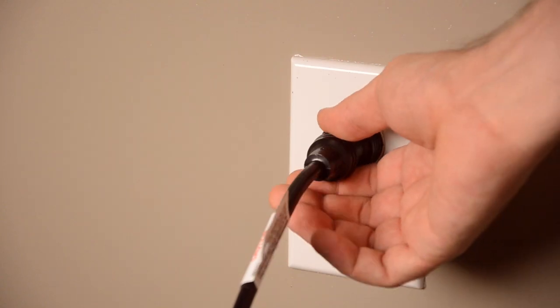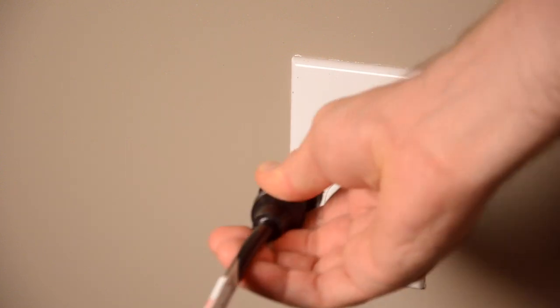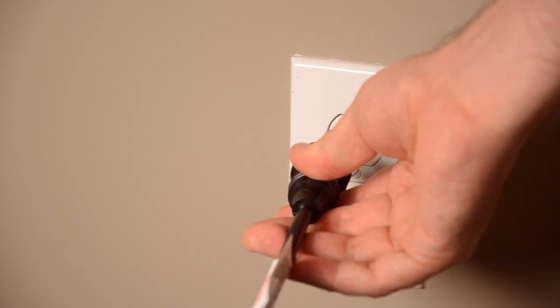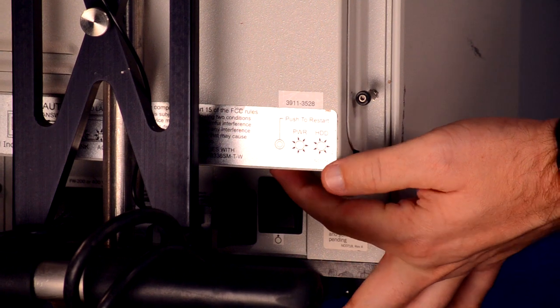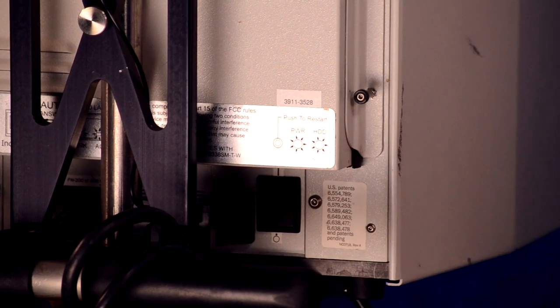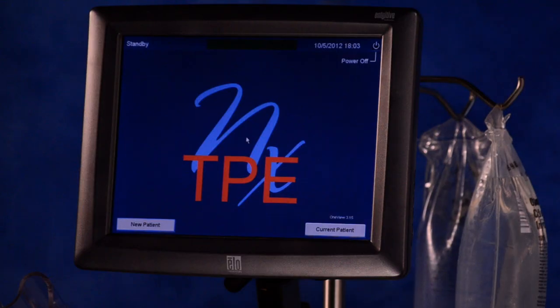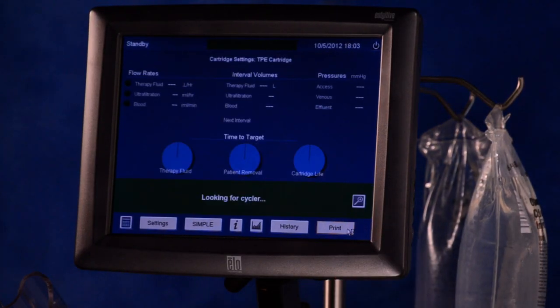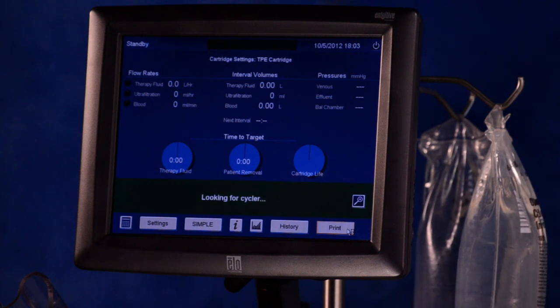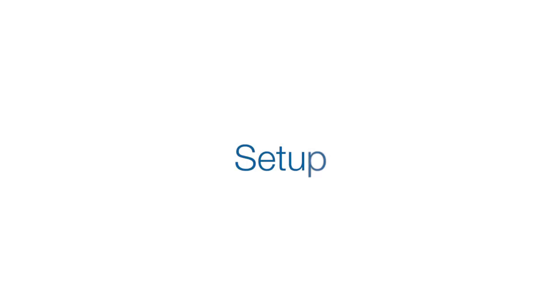Let's start by turning on the OneView. You can remove the power cord from the wall outlet and reinsert it, or depress the reset button on the jewel box. Wait for the standby screen, then choose new patient or current patient as appropriate. Follow the IFU or quick start note instructions.